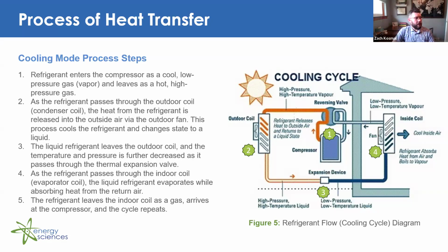As that refrigerant passes through the outdoor coil, in this case the condenser coil in cooling mode, the heat from the refrigerant is released into the outside air via the outdoor fan, and this process cools the refrigerant and it changes state from a gas to a liquid. Next, we move to step 3, our expansion device. This high pressure, high temperature liquid refrigerant leaves that outdoor coil, and the temperature and pressure is further decreased as it passes through that thermal expansion valve or expansion device.